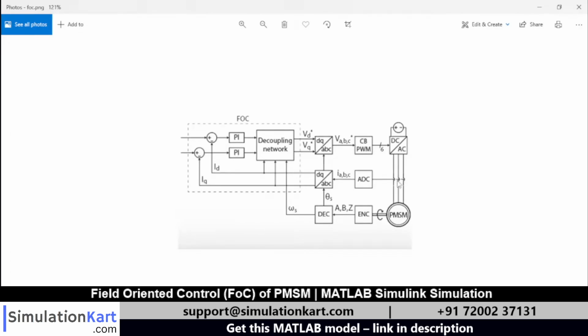The line currents are measured. The line currents are IA, IB and IC. All the three currents are measured and converted to dq axis currents. The actual value of ID should be 0, and the value of IQ comes from the previous block. It comes from the reference speed and the PI controller associated with that.